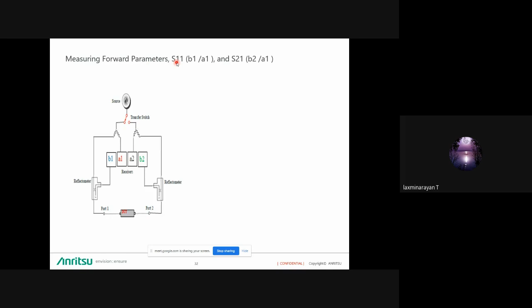So we can measure the forward parameters. What happens in the forward parameters? Like S11, B1 by A1, or S21, B2 by A1. As we know, A1 measures the incident energy onto the DUT. Whenever we consider S11, the switch shifts to port 1, the reference signal is in A1, and the signal is transmitted through a coupler and given to the DUT. Some signal is reflected back to B1, which measures the reflected energy. Some signal is transmitted to B2, which measures the transmission parameters. So taking A1 as a reference, we can measure the reflected signal at B1, and the transmission parameter can be measured using the B2 receiver, taking B2 by A1.